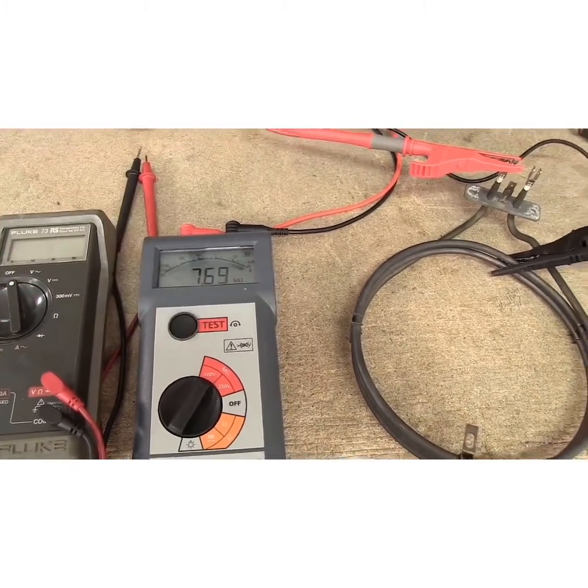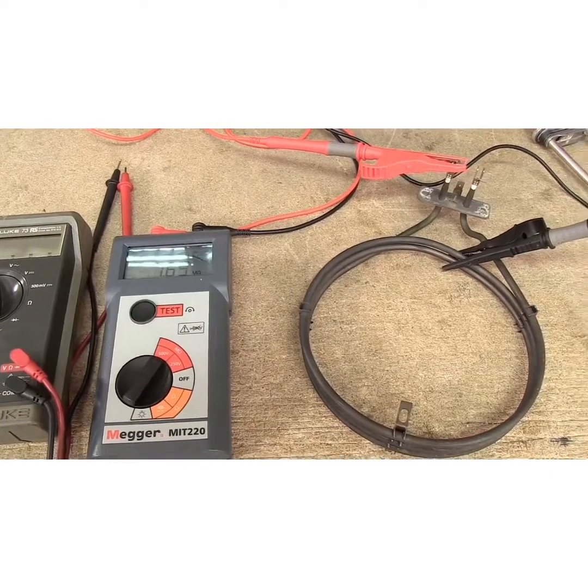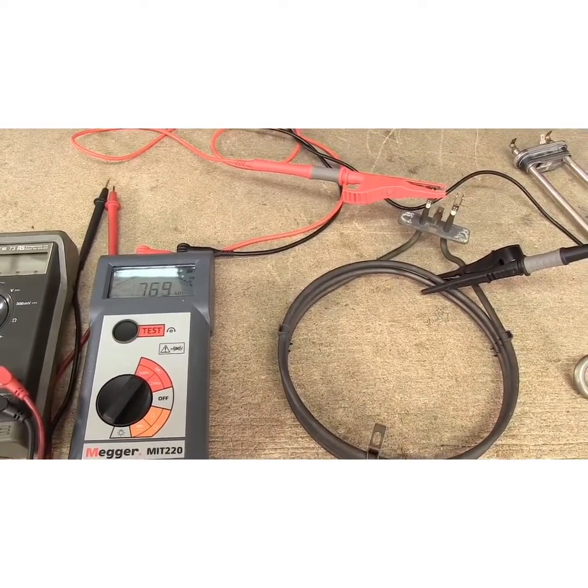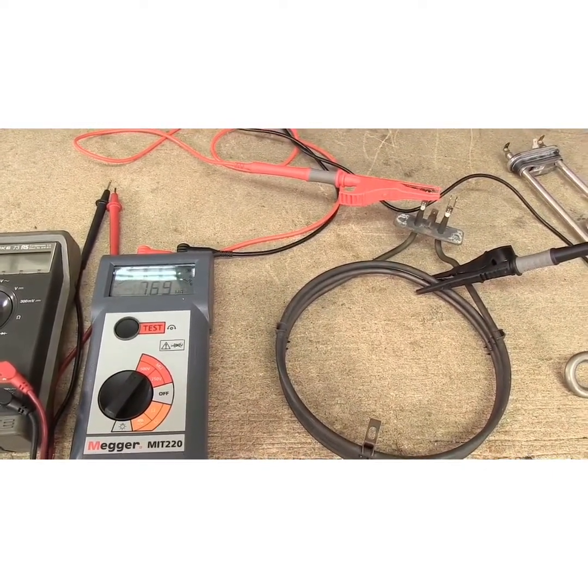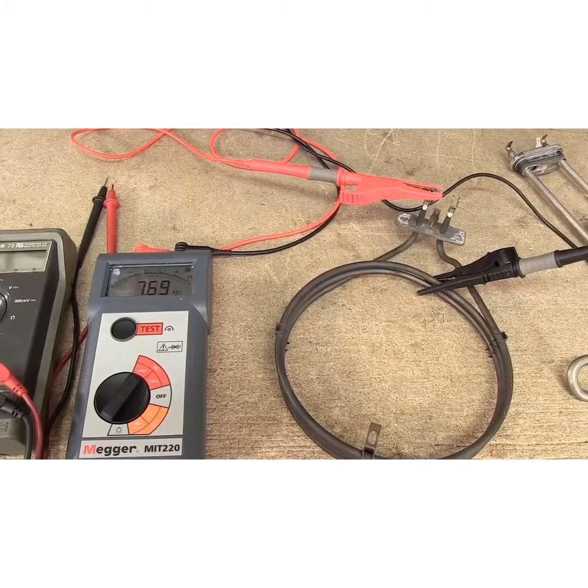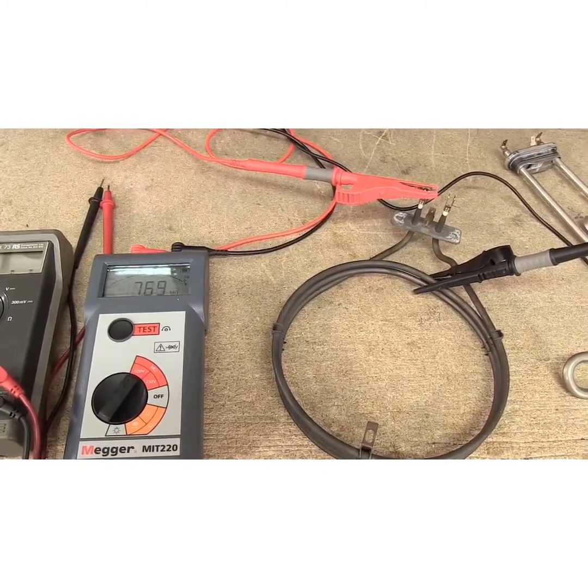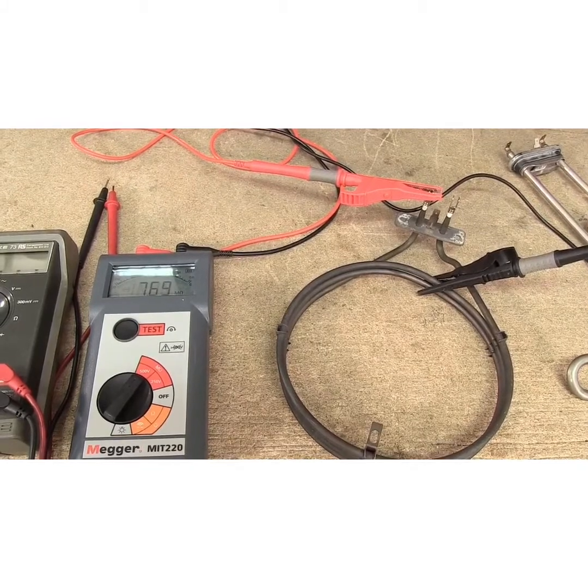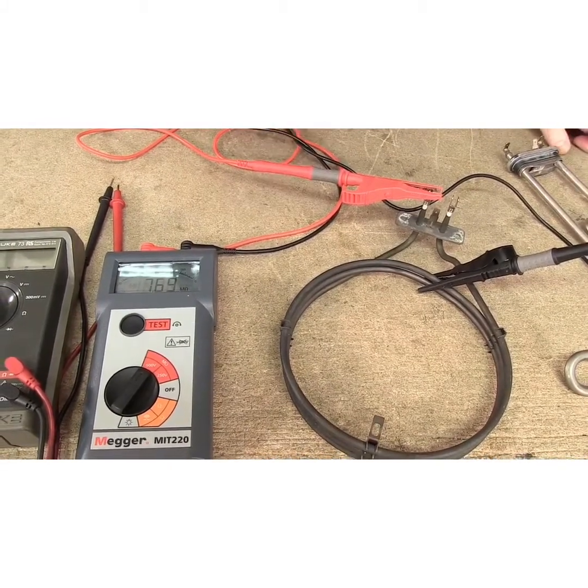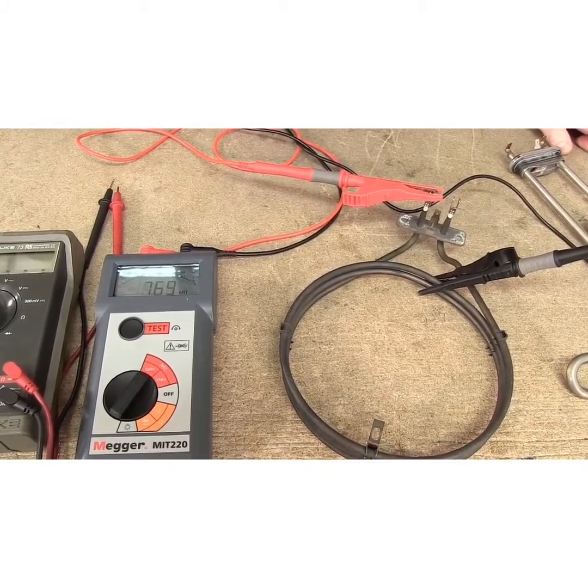If you have a reading of less than 2 megohms, this means the component is very likely to be tripping your electrical board at home. Whereas this one has a reading less than 1,000 megohms, but not as low as 2 megohms, meaning that although there is a fault in this component, given time it may develop into something that does trip your electrical board.